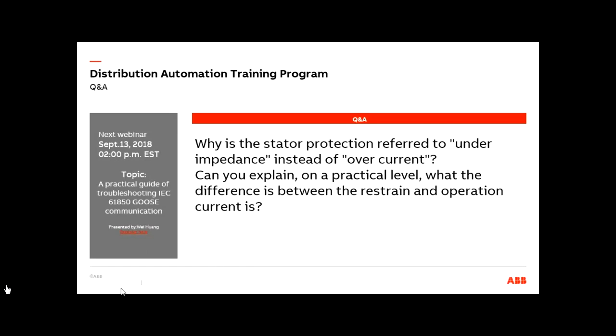The differential current is derived between the current at the terminal and the neutral side of the CTs, and then a bias current or restraint current is derived in order to provide more stability to the protection element. So it's basically a balancing act. In crude terms, the operating current will try to operate the element. The restraining current is connected in such a way, I'm talking now in terms of electromechanical relays, that it will oppose the operation of the relay. So both act in opposition.